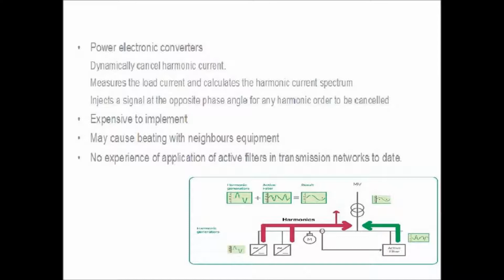So I suppose then there's active filters. These are quite different to the passive filters. Basically what they do is they measure the harmonic currents that are present on the system, and they work out exactly what's needed to cancel them out. So if you've got harmonic current at a certain phase, they'll put in one that's the exact opposite phase and it'll cancel itself out. The problem is that they're very expensive to implement, and there's not that many of them around. I don't know of any on any transmission network yet, but I'm sure they're coming down the line. And the other thing is that if you've got one very close to another one, it can actually interact with the neighbouring equipment, so you could end up with a beating effect, and they could end up actually making things worse. So you have to be very careful when designing active filters.